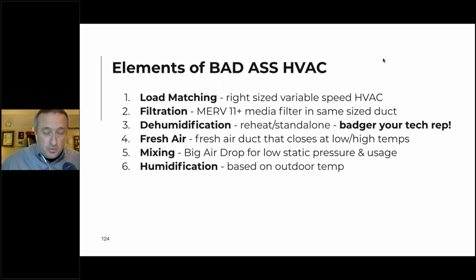You need a right size variable speed piece of equipment. Filtration, you need at least a MERV 11 - with COVID, you need at least a MERV 13. Dehumidification, you need to be able to do reheat or have a separate standalone unit. If the manufacturer you use doesn't have it, please annoy the hell out of them. Say, I want reheat dehumidification, just add it, Nate said so.